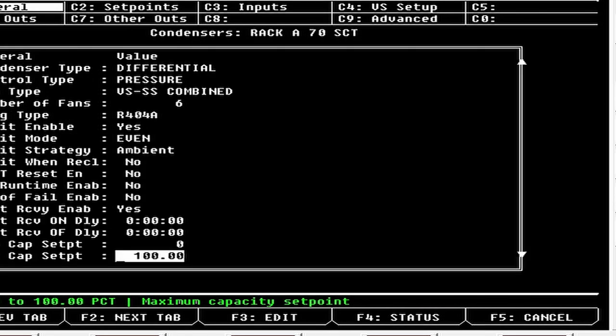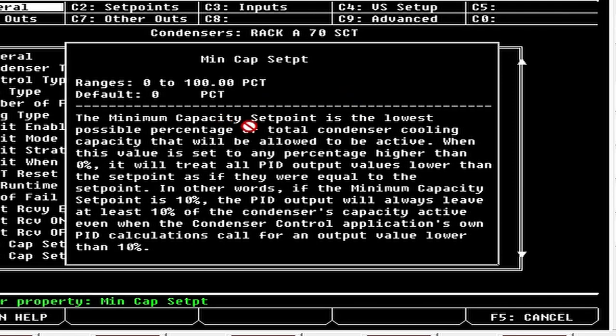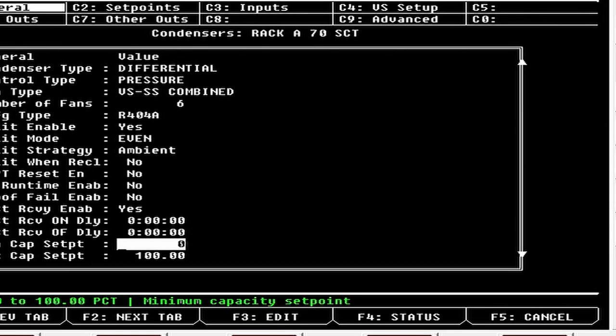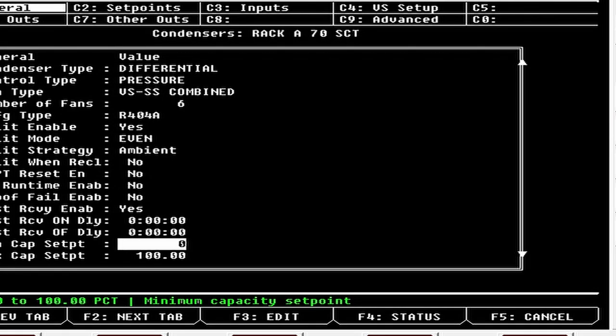Minimum Capacity Set Point and Max Capacity Set Point: if the minimum capacity is not set to zero, it treats all PID output values lower than that set point as if they equal the set point. So if minimum capacity is 10%, the PID will always leave at least 10% of condenser capacity on. I see a lot of guys set this at 10 and it causes tons of issues in winter because the condenser won't go lower — it may leave a fan motor or drive running when you need to kill the condenser completely at minus 10 outside. I always set that to zero.